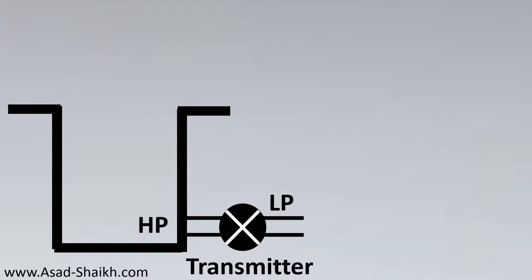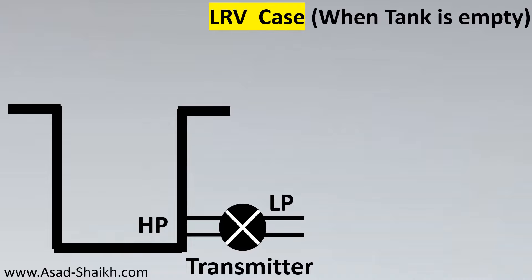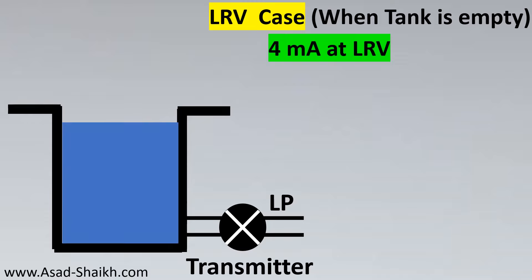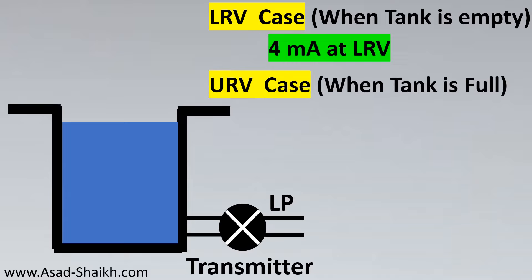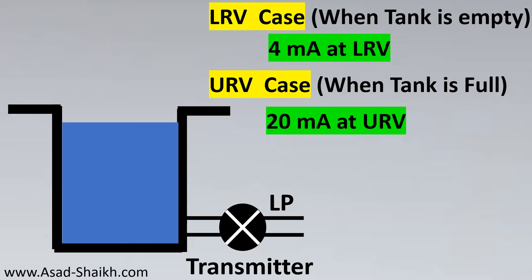To calibrate a transmitter we need two conditions. The first is called the LRV case, where the tank is empty — the transmitter should give 4 mA. The second is the URV case, where the tank is completely full — the transmitter should give 20 mA. This is our calibration range.